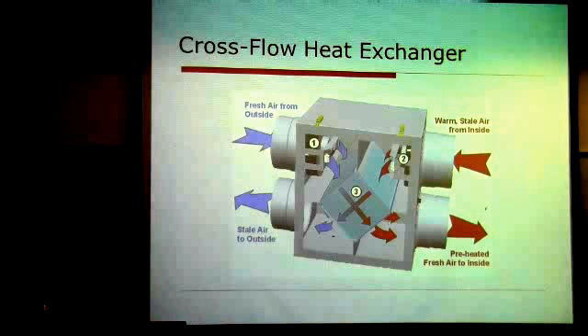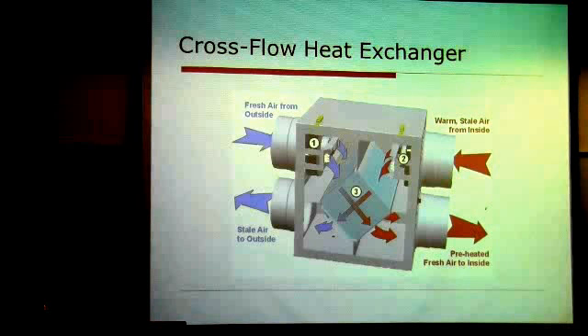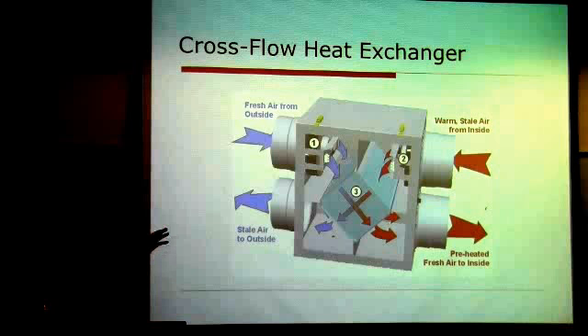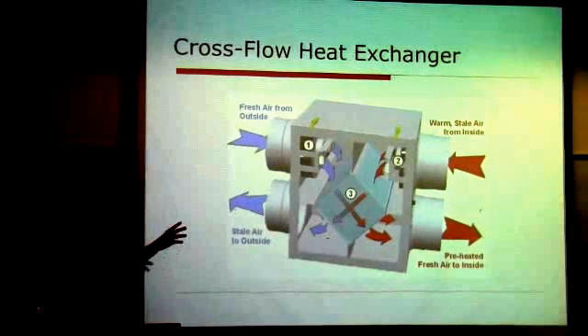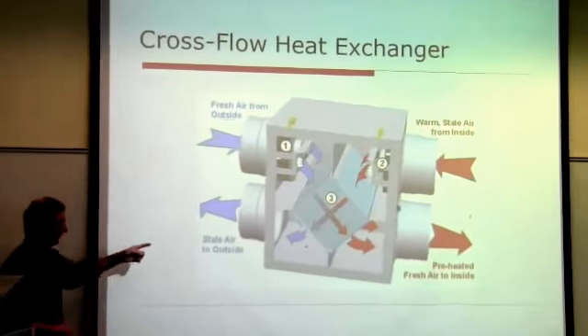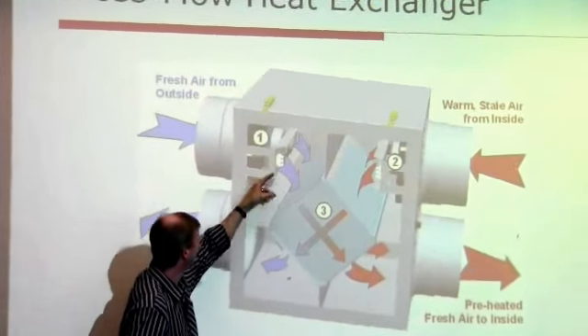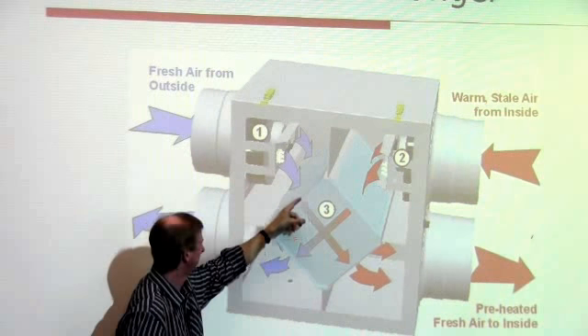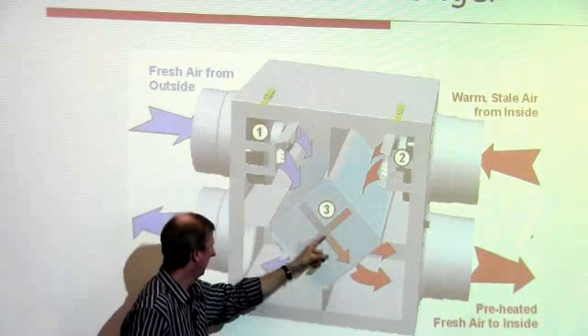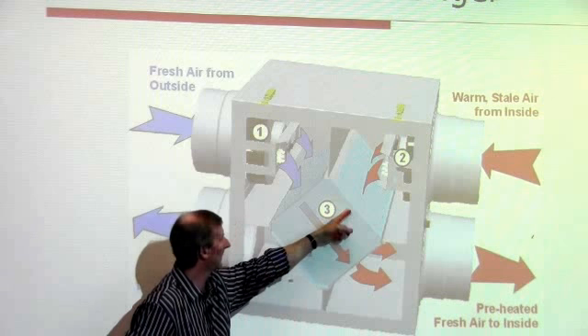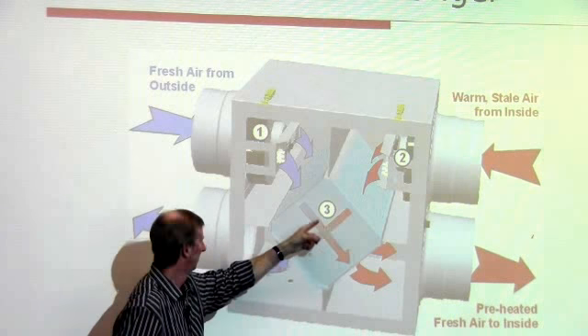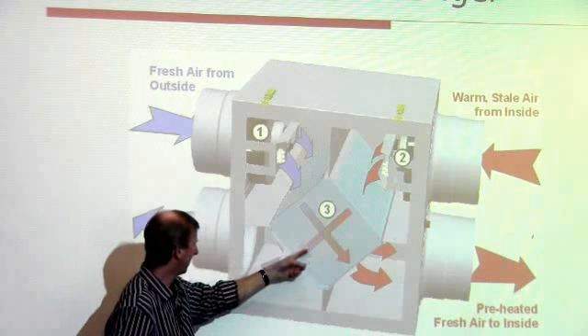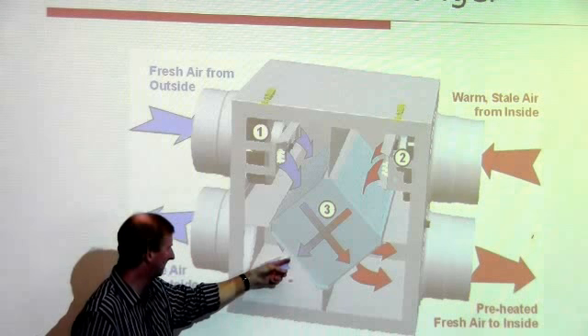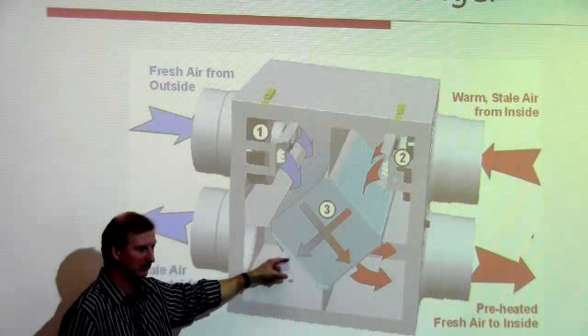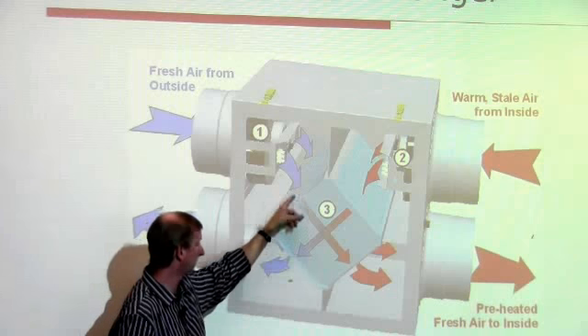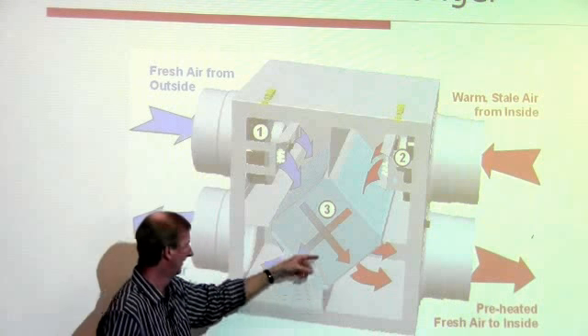A few types of HRVs. This one's a cross flow. And this one would be maybe 65, 75% efficient. And where it loses, so say this is cold air coming in from the outside, say it's 40 degrees here, and say this is coming out from the house, so it's 70 degrees. The 70 degrees is cooling off as it goes across, and it might get down to, say, 50 degrees here. So it's losing 20 degrees, where this one might be increasing 20 degrees.